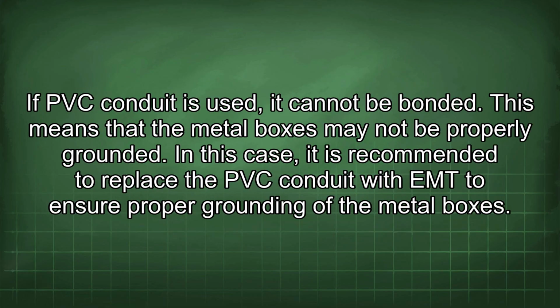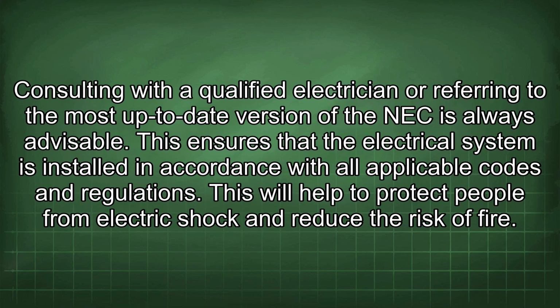If PVC conduit is used, it cannot be bonded. This means that the metal boxes may not be properly grounded. In this case, it is recommended to replace the PVC conduit with EMT to ensure proper grounding of the metal boxes. Consulting with a qualified electrician or referring to the most up-to-date version of the NEC is always advisable. This ensures that the electrical system is installed in accordance with all applicable codes and regulations. This will help to protect people from electric shock and reduce the risk of fire.